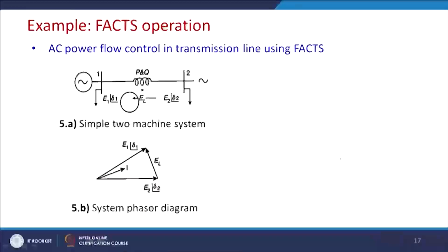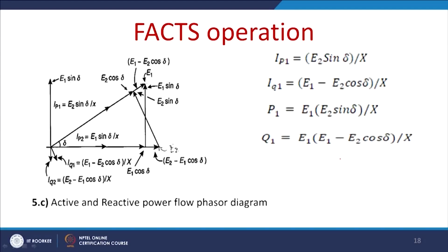Now, let us come again to the two machine model, and we assume, and this is a phasor diagram of it, that the angle between them is delta and I is almost perpendicular to the EL. Now, we shall calculate the power at the receiving end, and in the same way we can calculate the power at the sending end. So, this is E1 and this is E2, and the angle between them is delta. The real power component of the sending end current is given by E2 sin delta by X. Similarly, the reactive component of the current is given by E1 minus E2 cos delta by X. So, P1 equals E1 E2 sin delta by X. This is the sending end power.